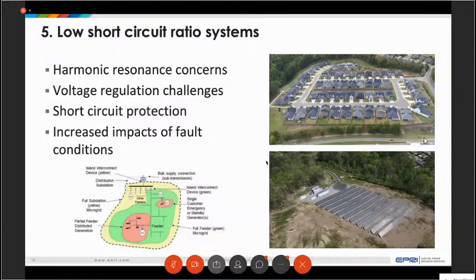This becomes particularly important in microgrids, where when a microgrid goes from being connected to a grid with higher short circuit capacity to running on its local system, where generation might be PV, batteries, and maybe a fuel cell, we have to change the way we do protection.